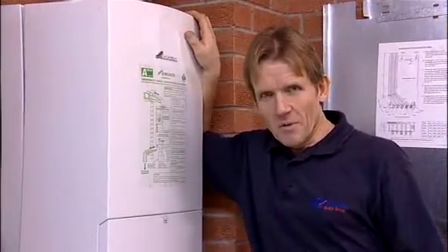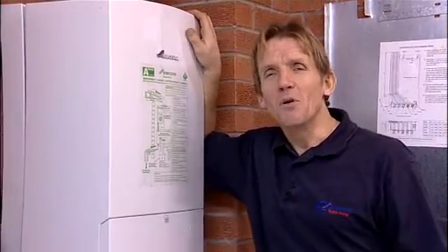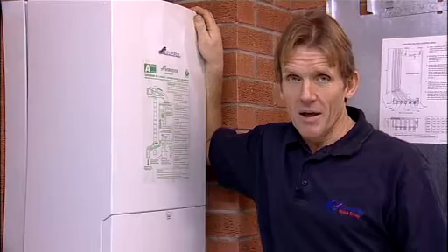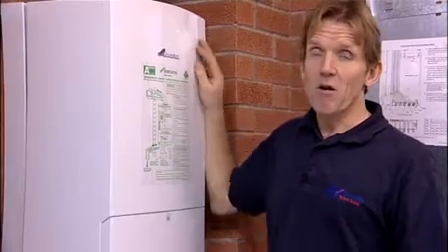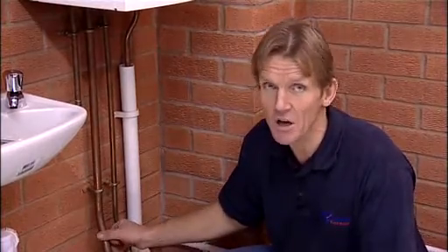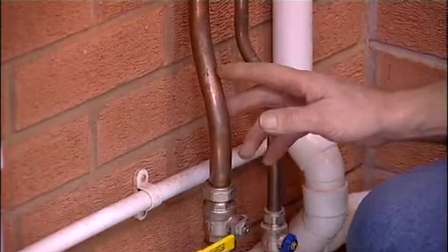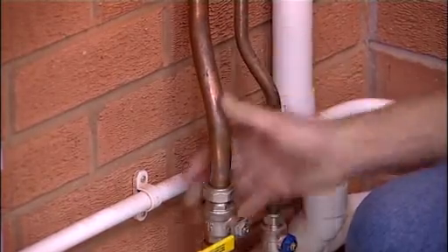Now it might sound obvious, but another fault that you get with gas boilers is the gas supply. It needs to be big enough, and very often people overlook this fact that you need anything around sort of 20 millibars of working pressure. Now I emphasize working pressure because sometimes people just check the static pressure and assume that it'll be okay. And of course when the cooker comes on, the boiler dies, or when the boiler comes on, the cooker goes out. So you need to check the supply is big enough to supply all the gas appliances simultaneously.